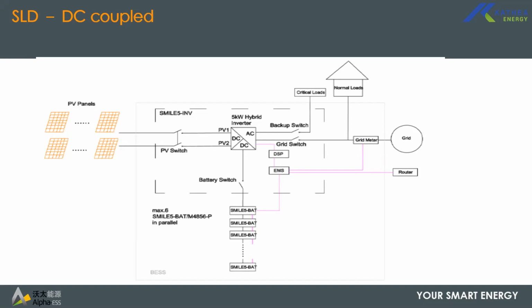And then from the inverter, we have the output, which is the backup port, where you wire your critical loads. Please try and avoid inductive loads on the critical side because of their starting current. They can easily overload the unit when it's changing over to UPS mode. It's 20 milliseconds. So definitely the grid has to lose power, and then inverter power comes on. During that 20 millisecond period, if you have inductive loads, they will draw an inrush current, that is starting currents, to compensate for the dip in voltage, and that could actually cause overload on the inverter. So if you have inductive loads connected on your critical load side, you would find yourself in most scenarios having the system restarting between waiting and checking continuously.